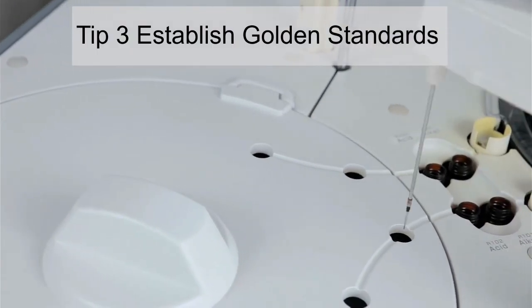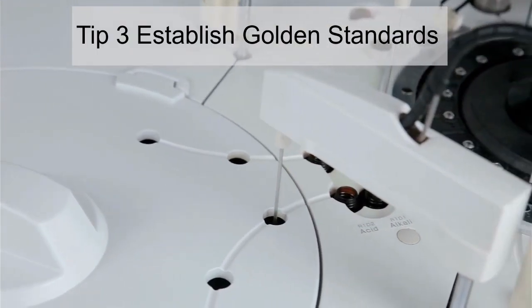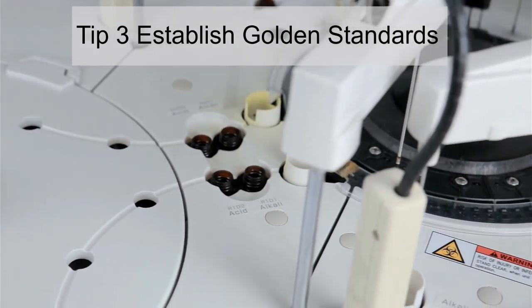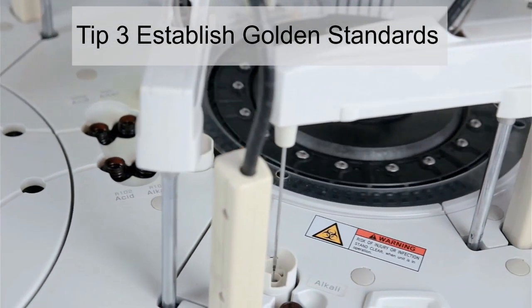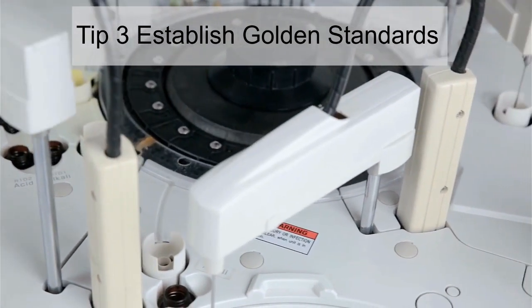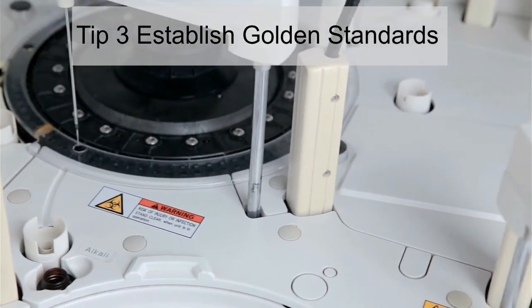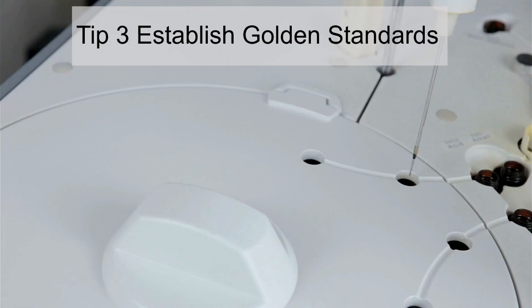Tip number 3 would be to establish the golden standards. Golden standards are used to verify the measuring equipment's ability to measure accurately. A measuring equipment should be verified with a known measurement golden standard at a regular interval. An accurate golden standard must be established to cover the range of the measurement, and it should be properly maintained.